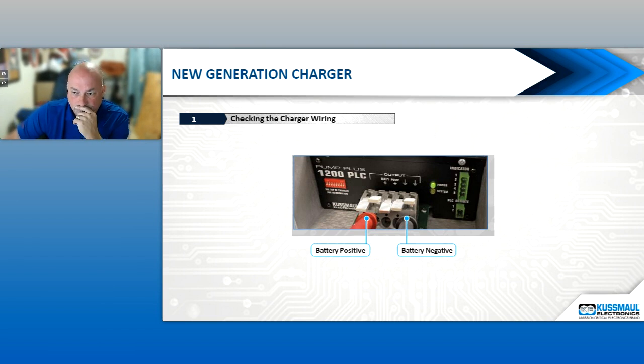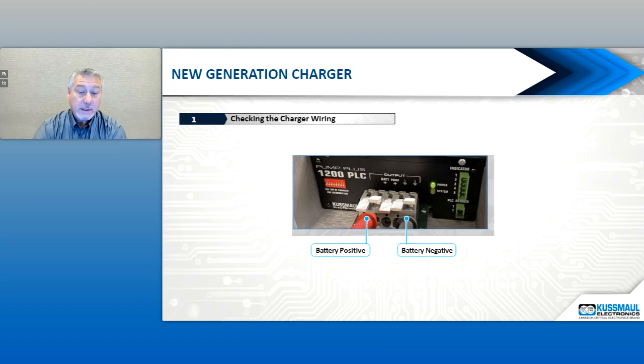I don't think the indicator screen actually reads incorrectly. I have seen screens go bad before - it is a man-made product, things go wrong. What's probably more likely is that little connector, or one of the tiny wires came off of it somewhere, and it's not reading correctly. That's not to say there couldn't be a bad indicator. If that's the case, you can contact Kussmaul, and we can help with some testing and get you another indicator if we believe it's faulty. But I think most of the problems are not the indicator - it's probably the wiring, or it's actually reporting correctly and people just don't trust that it's correct.